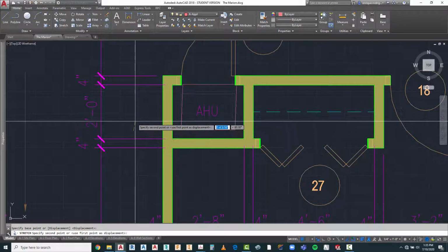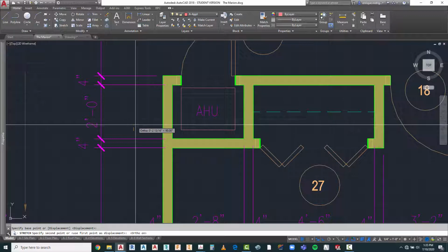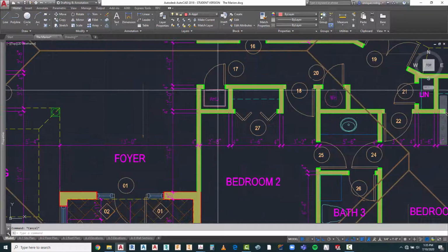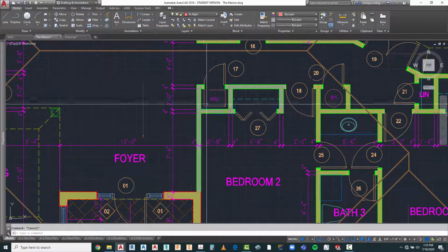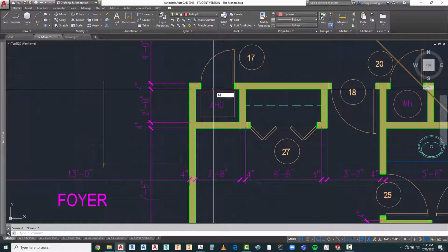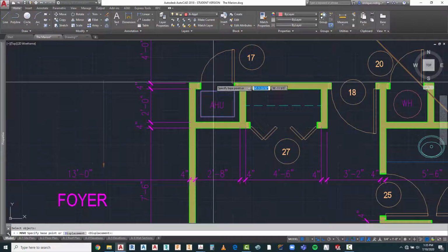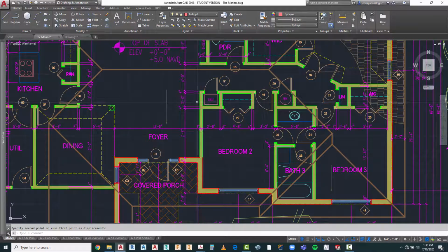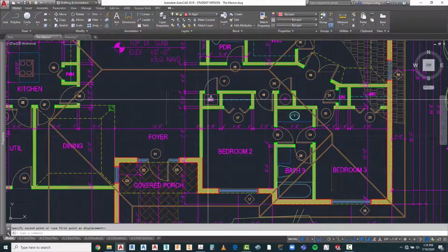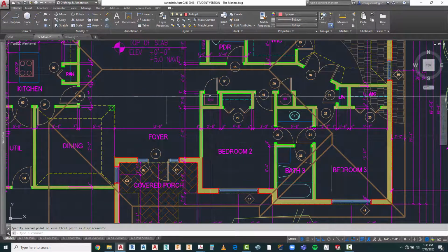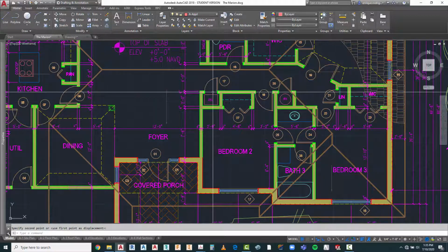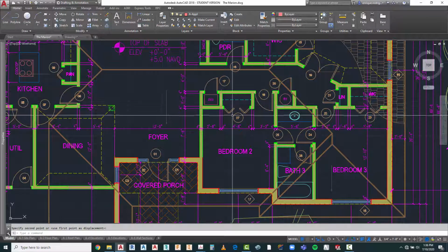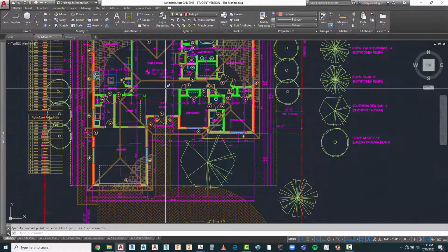So we would have to coordinate with the air conditioning contractor or the AC engineer to make sure that we've got enough room that meets all the code requirements in terms of clearances, etc., before we size this one out. This also gives us the opportunity to have a return air grill here, or to have one coming in from the top, or actually use a louvered door for that. So at least now we've got a water heater and an air handling unit.